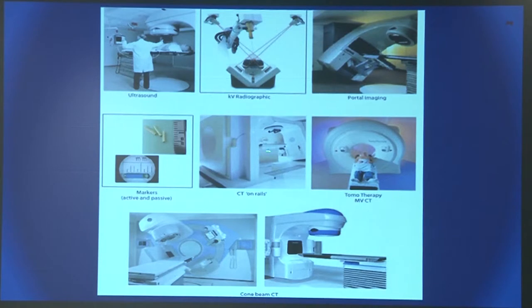CT on rails basically has a CT scan inbuilt opposite to the treatment machine. So the patient, on any particular treatment day, lies on the couch, moves onto the CT machine, takes a CT scan, and the same information is used after the patient moves back into the treatment machine. So this is a CT scanner, this is a treatment machine, and the couch runs between them—that's why it's called CT on rails.